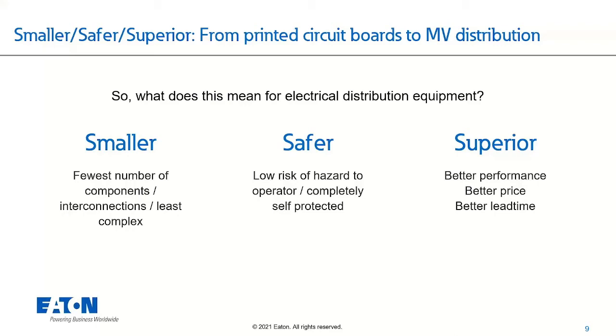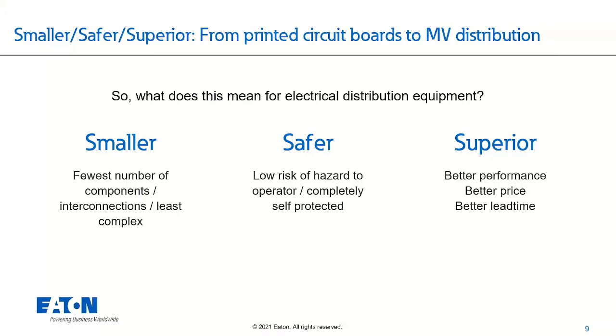Imagine a low voltage assembly where an arc flash incident occurs that's relatively safe for the user, their arc flash boundary is enough that they're in a pretty safe scenario, but the equipment damage is still fairly high at that level 2 zone. That matters because I want to know how I get that equipment back online, what the total capital cost is, and downtime and outages are another very big piece. So, how can I increase safety not only for my operator but also for my equipment, ideally increasing its longevity and keeping repair costs as low as possible.